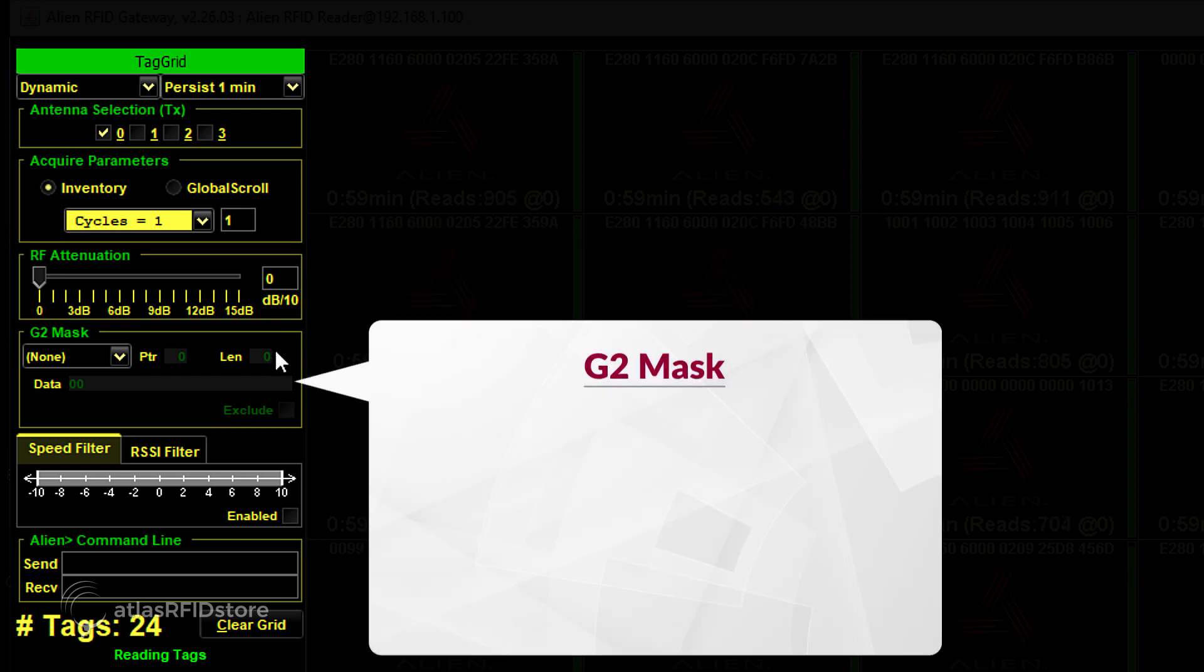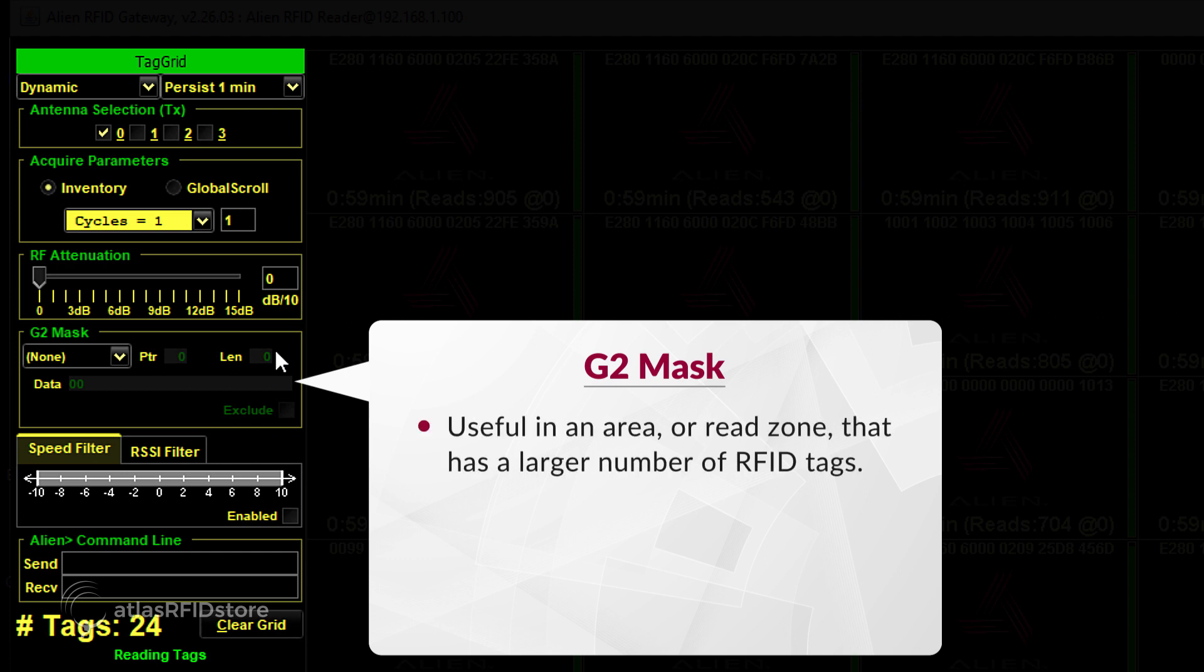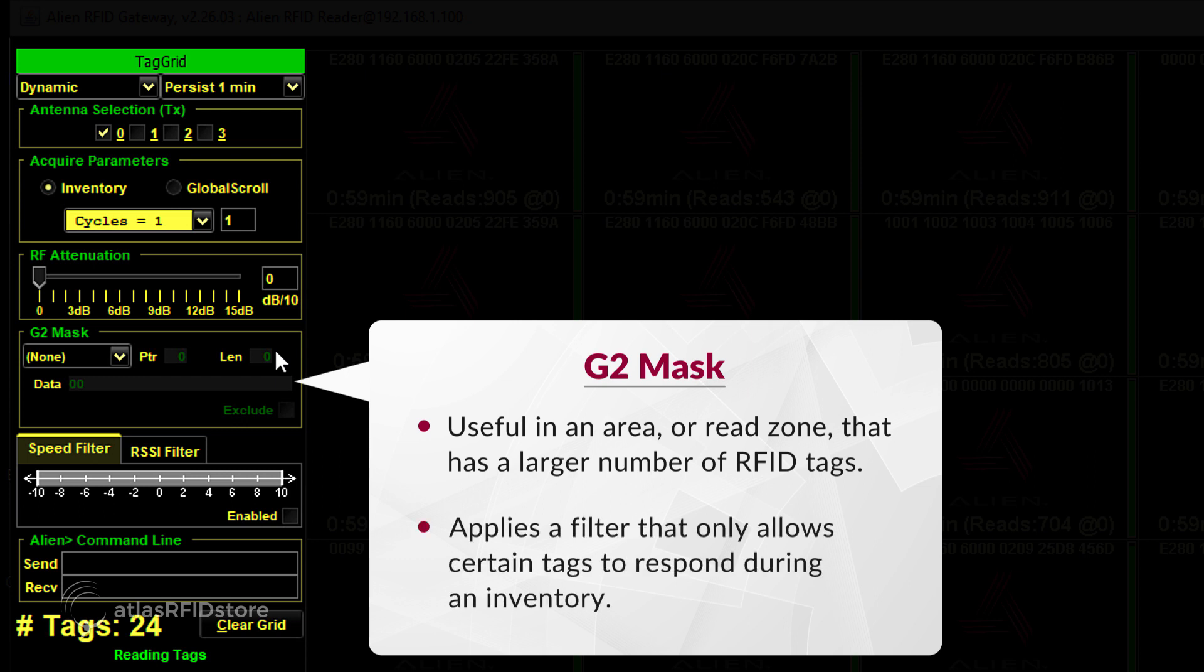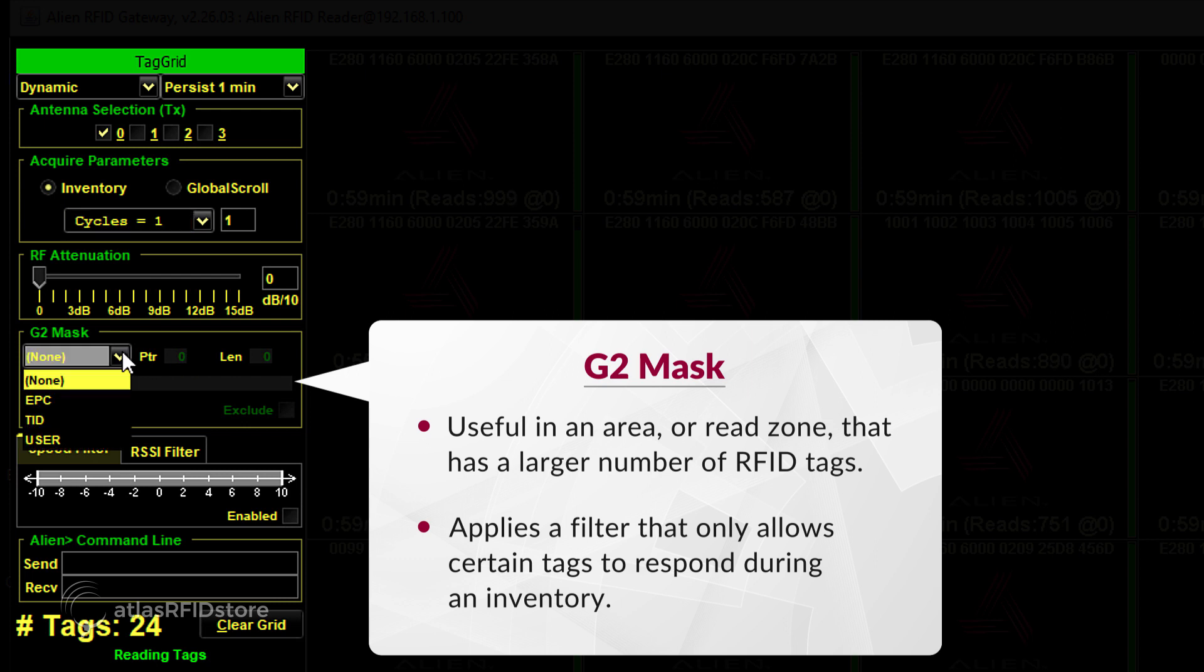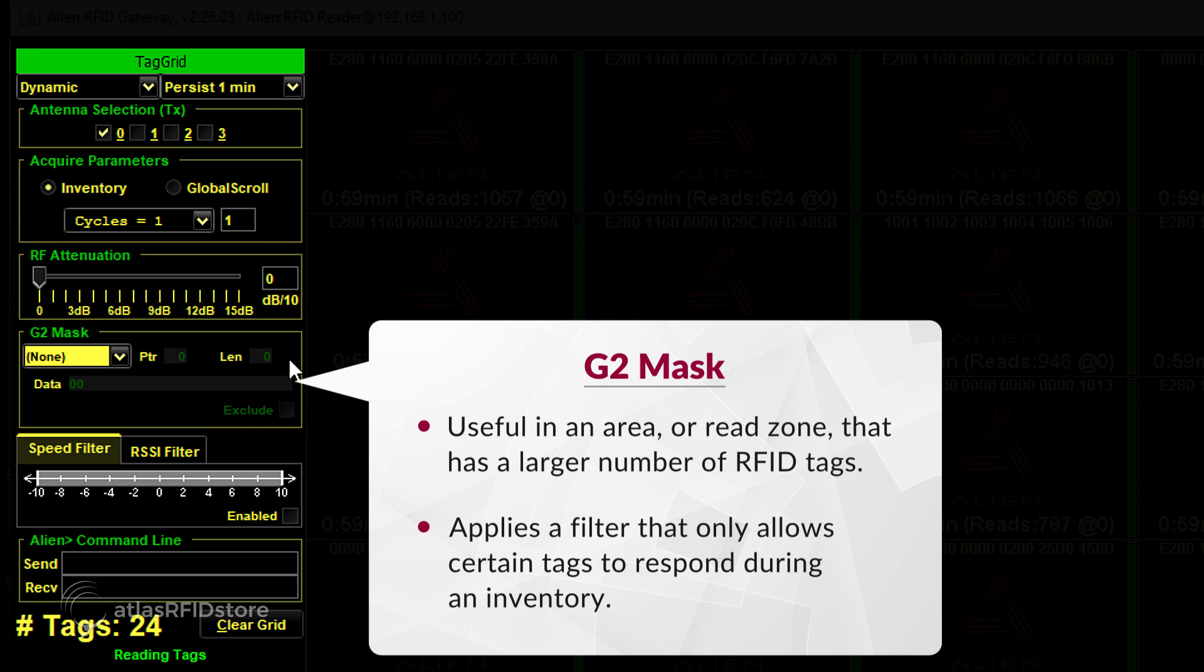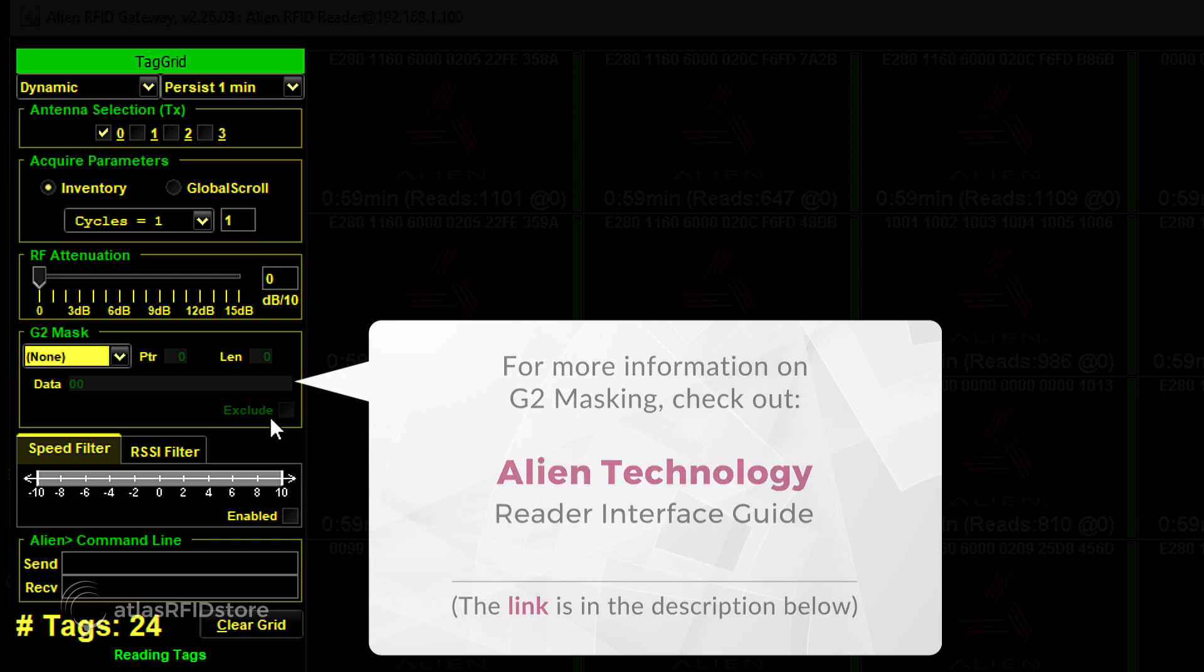G2 Mask is the fourth box in the Property Panel. This can be a very useful tool in an area or read zone that has a large number of RFID tags. Basically, a G2 mask applies a filter that only allows certain tags to respond during an inventory. With the first dropdown, you can choose a memory bank to filter with, then at what bit number you want the mask to start, and the length of the mask in bits. You can also check the exclude box so that the filter only includes tags that don't match the intended mask. For more information on G2 masking, check out Alien's Reader Interface Guide.